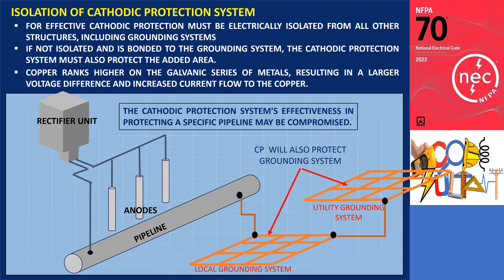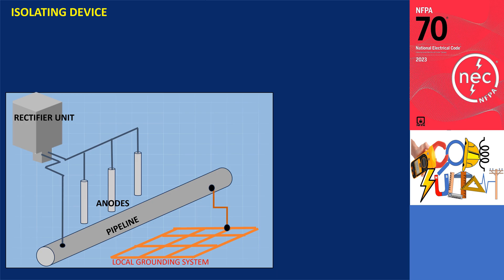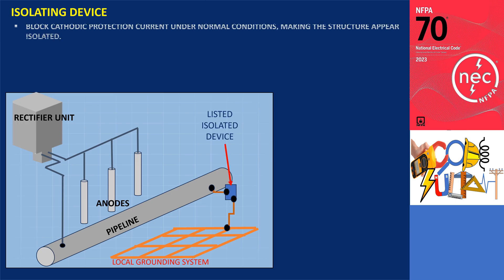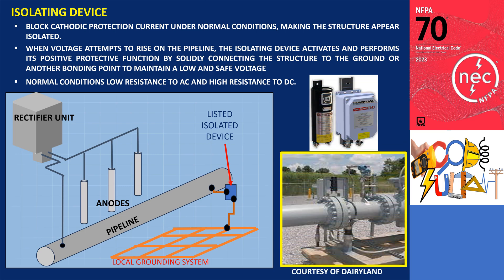This is one reason why isolating a cathodically protected pipeline is necessary. However, electrical codes require that metals susceptible to becoming energized, such as during lightning strikes or surges, be grounded and bonded to achieve equipotential. This is accomplished by installing a listed isolator device. The purpose of this device is to block cathodic protection current under normal conditions, making the structure appear isolated. However, when voltage attempts to rise on the pipeline, the isolating device activates and solidly connects the structure to the ground or another bonding point to maintain a low and safe voltage. Once the event is over, the device automatically switches back to its normal mode of blocking DC. Under normal conditions, this device exhibits low resistance to AC and high resistance to DC. The provided photo serves as an example of an installed decoupler by Dairyland, showcasing such a device in practice. Thank you all for watching.